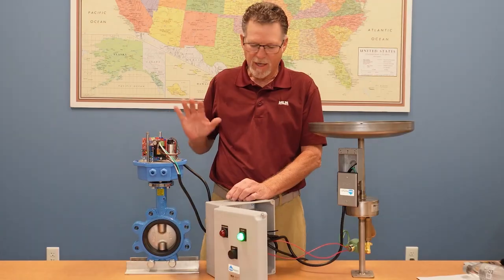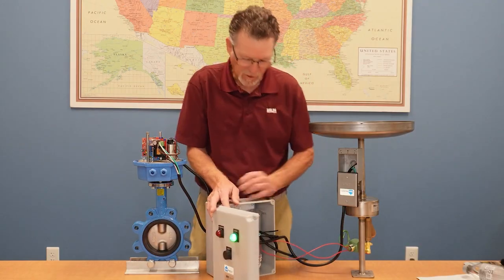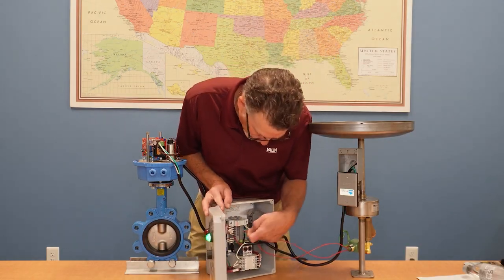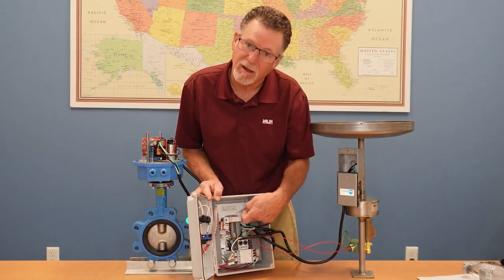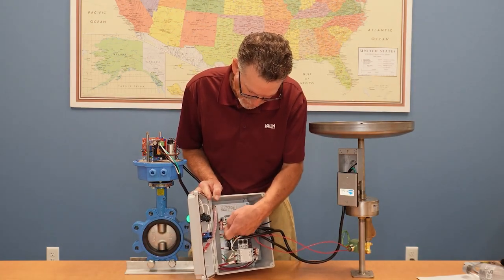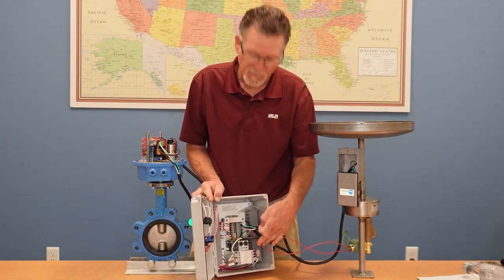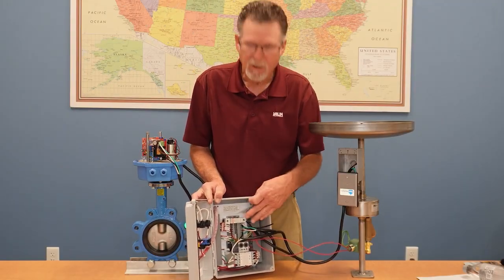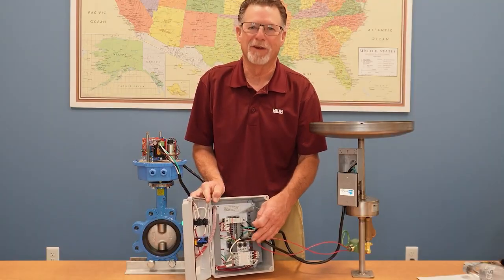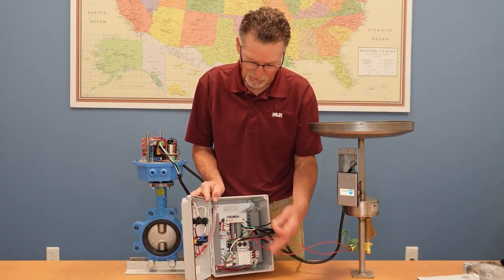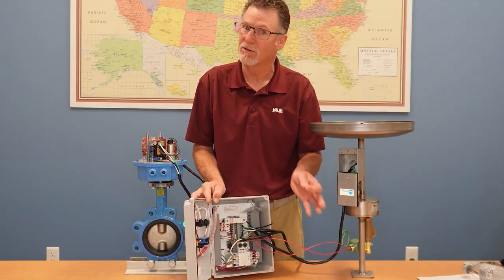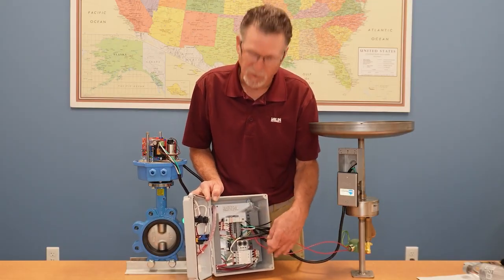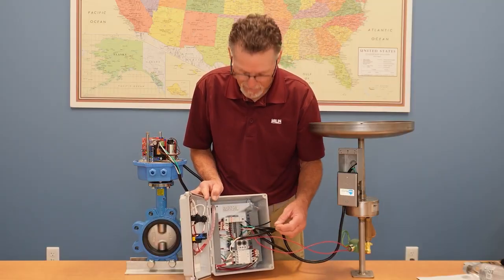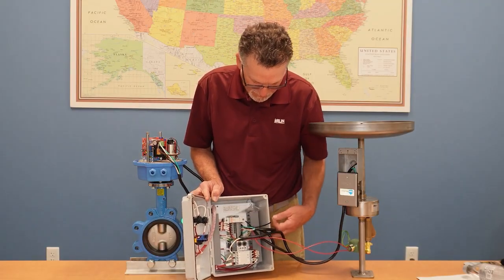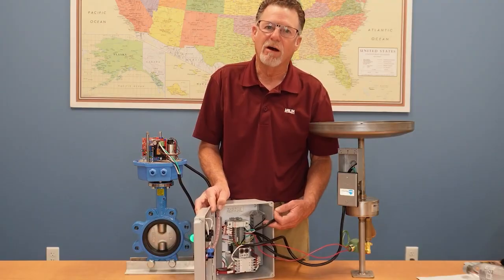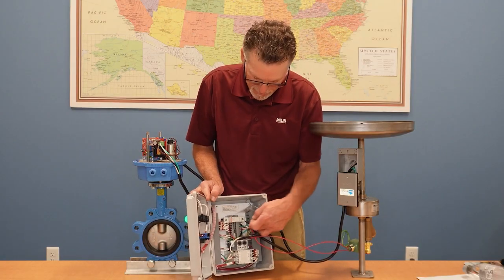If the valve's not actuating, I typically will have you remove all the field side of the terminals. This is the factory wiring. This is your field wiring. Obviously, I have a rat's nest of wires here right now just for testing it. But normally you're going to have everything run through conduit, sealed conduit, so it'll obviously be a lot cleaner than what we have here. But I would typically remove all the wiring going to the valve. And then you can check voltage.